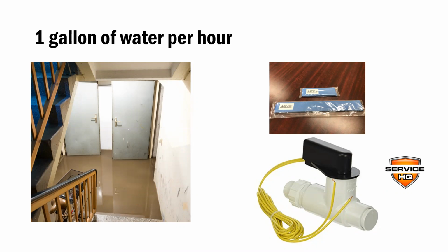So if we do a maintenance, we always offer a drain pan treatment and a drain line safety switch. What this thing does is we actually wire it into the cooling system. So if for any reason the drain line gets clogged, it's going to shut the system off and stop producing water so it doesn't continue to create a flood. Now, when it shuts the system off, that alerts you to know, hey, I have a problem because my unit's not cooling. And then we could come out and blow the drain line out and get it functioning again. But it's just a safety to keep this from happening.